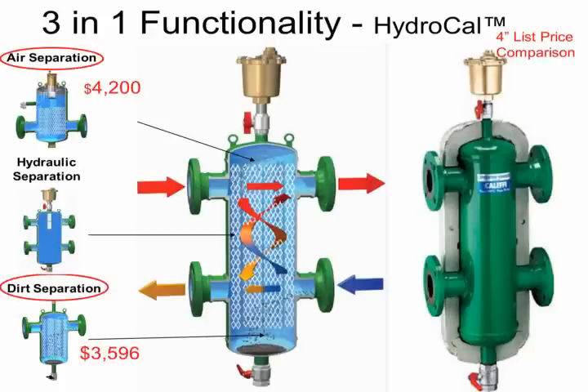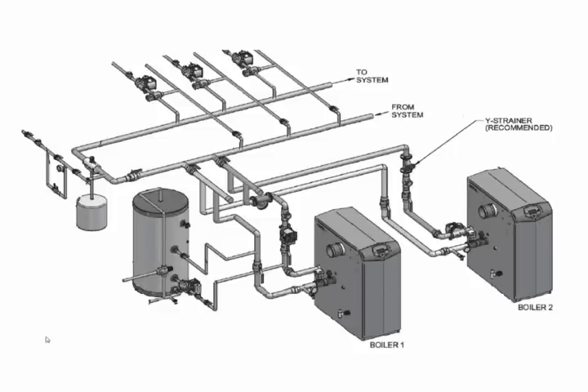So as we've introduced this, why does it make sense? Well, it's the same argument as we showed in the 2-in-1 device. The 3-in-1 device is very economical. Even if you aren't worried about dirt separation, and you simply want to do hydraulic separation and air separation, economically you can justify using a 3-in-1 device in place, and you get the dirt separation to boot.